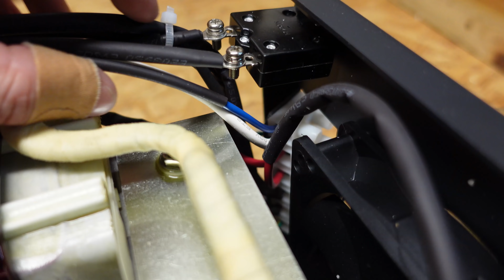These two are the power input wires. They are number 12, which at 6,000 watts would be about 25 amps. And I would have preferred to see number 10s everywhere, but they're still within spec for chassis wiring, and the insulation is rated for 105 degrees Celsius.